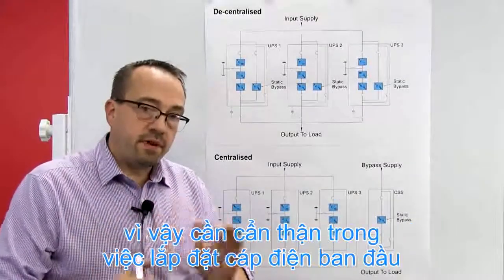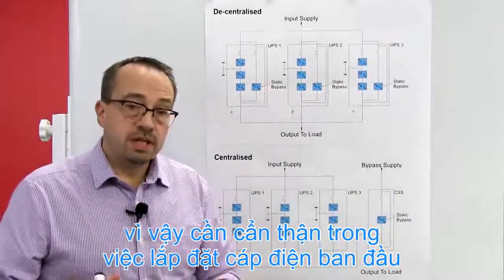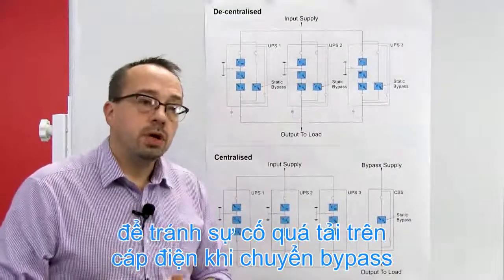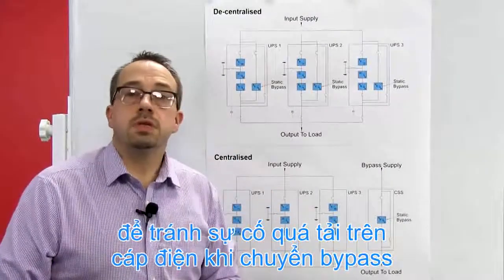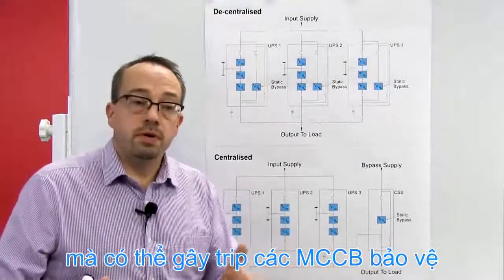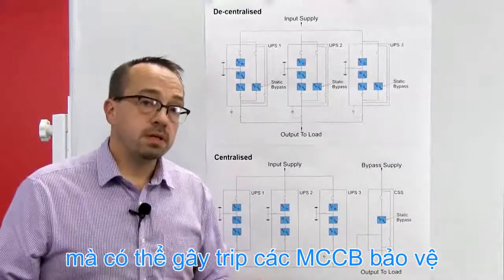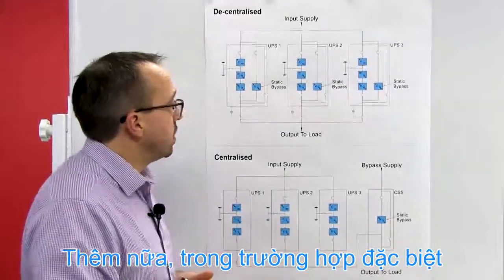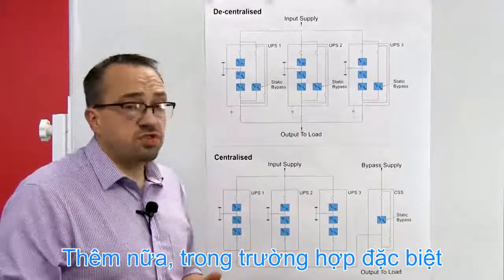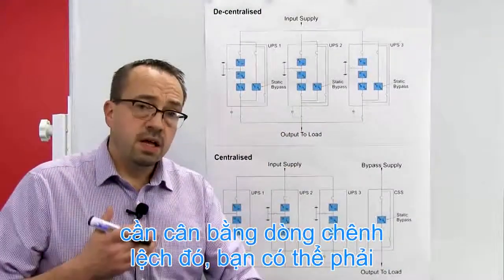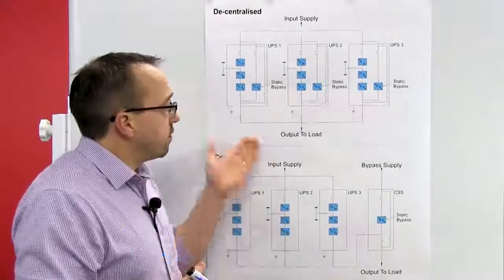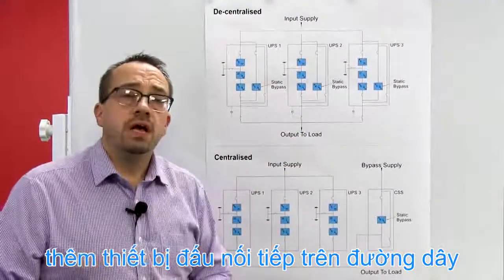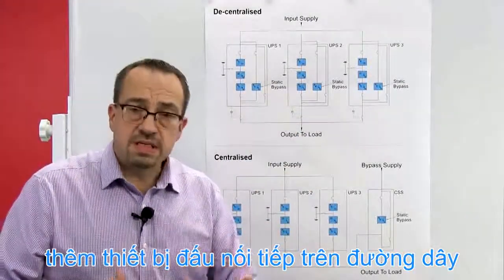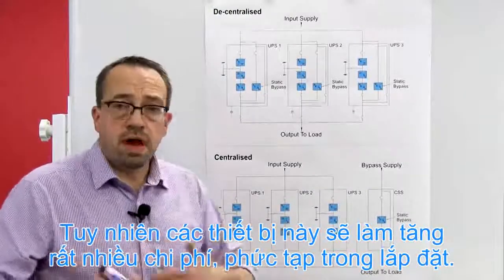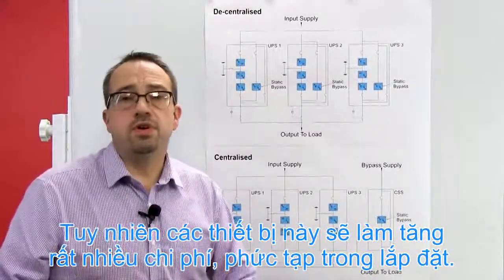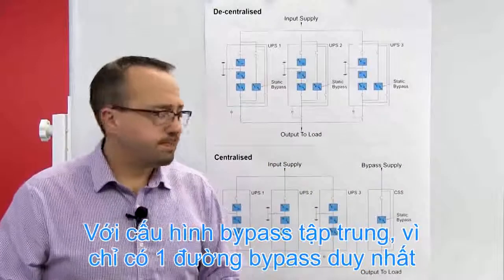Now, if that's not carefully installed from day 1, potentially during bypass operation, you could overload some conductors and therefore cause inadvertent nuisance tripping of the supply circuit breakers. So that's something you need to consider. In addition to that, during extreme circumstances, in order to aid the balancing of that current, you may have to fit line reactors in order to facilitate the balancing. However, line reactors would add a significant cost increase to the overall system.